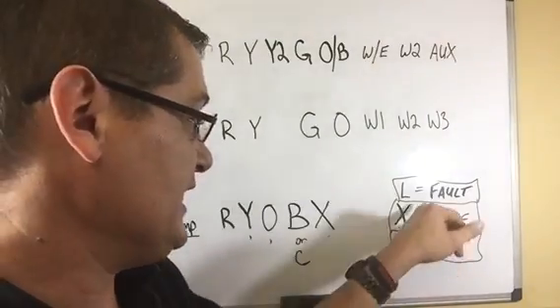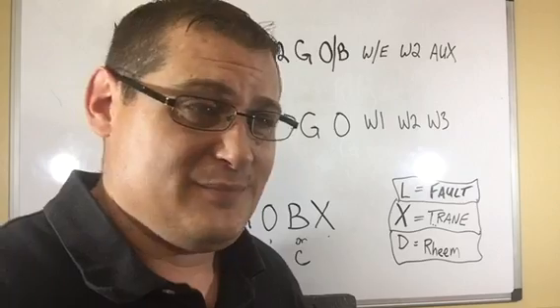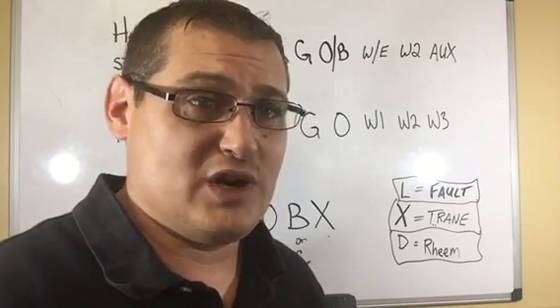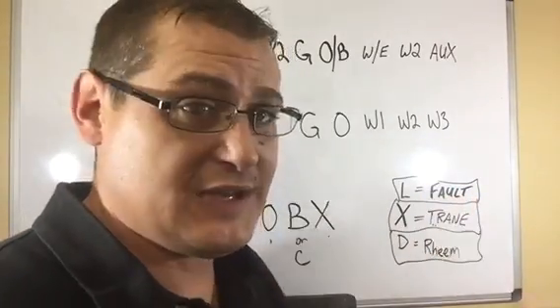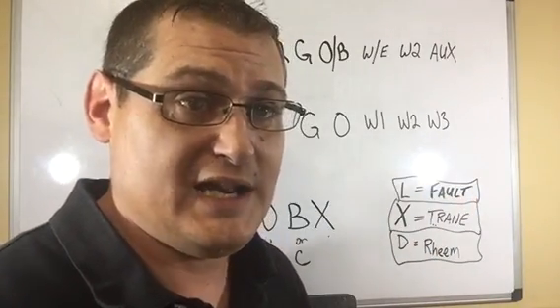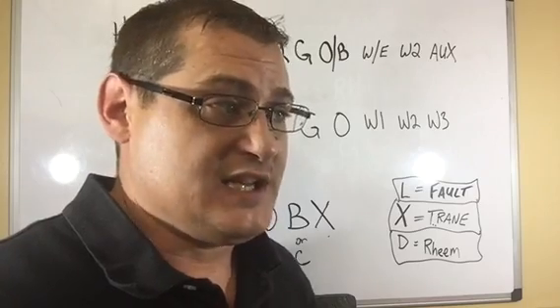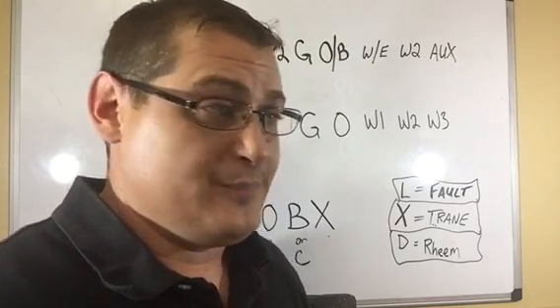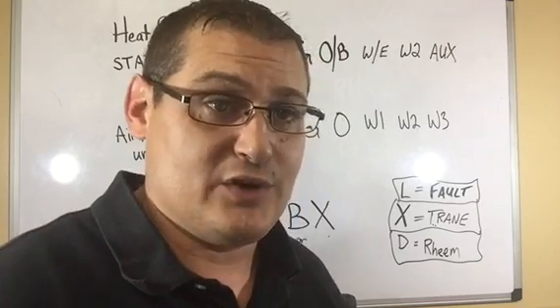I want to talk about a few other terminals here that you may see and just what they do. You may see an L terminal. I think York is still using L, possibly maybe Carrier. It really doesn't matter, as long as you know what it does. The L terminal, if you ever see that in a thermostat or outside, is typically the fault terminal. That means it's going to send power up to the thermostat if there's a fault outside the outdoor unit. All it does is light up a light in the thermostat.